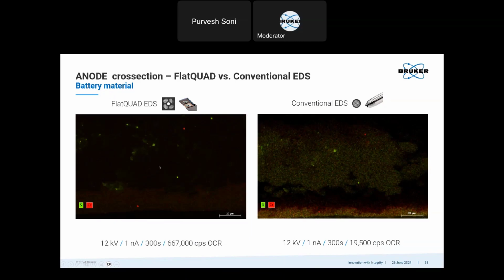And because of the high signal to noise ratio and also the 4-segment design, I could see particles which were there, but the data was not there because of the inclined detector geometry. So here you can see these two particles. They can be seen with the FlatQuAD, but with a conventional detector, we cannot see them. And here also you can see that the difference between the noise, which is in this region, and the signal is almost the same. So that's why you see more noise, but the signal to noise ratio is very good for the FlatQuAD, and that's why we could see these particles very nicely.